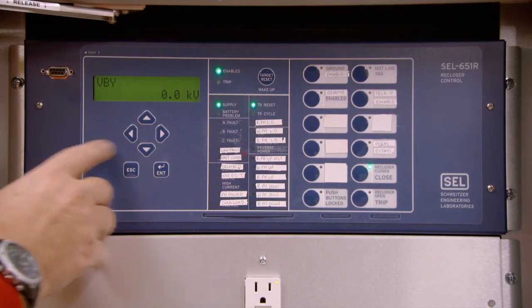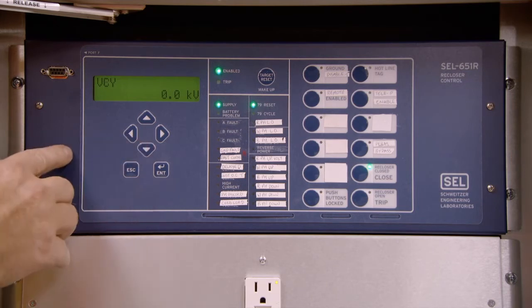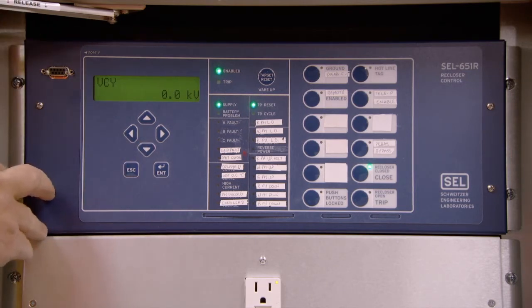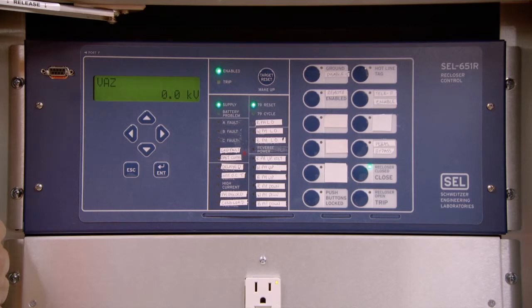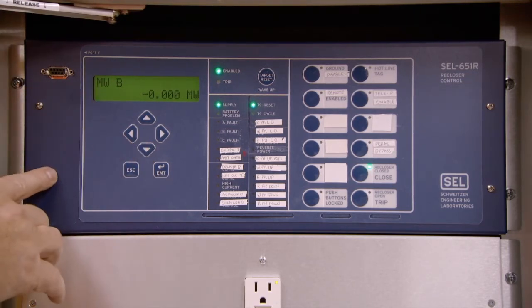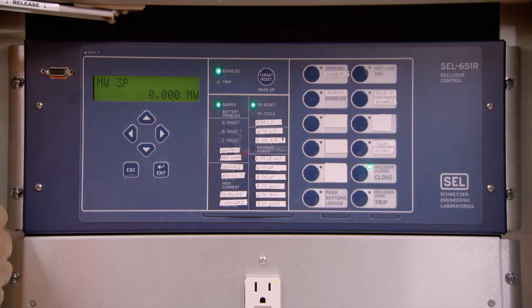Additionally, VBY and VCY, the following two screens, will give you all the voltage presence on the actual recloser itself. The next down arrow button takes us to VAZ, the letter Z referring to external potential transformers. If supplied, this would give you a rated value in the bottom right-hand corner of the screen. The next meter readout is MWA. That refers to the megawatts of the A-phase amperage. MWA is followed by MWB and MWC, and finally MW3P for the three phases. This concludes all the metering needs, all of which are accessible through the front panel.